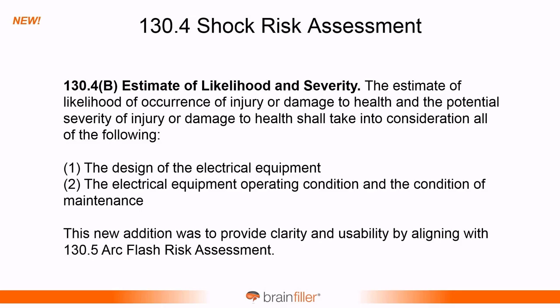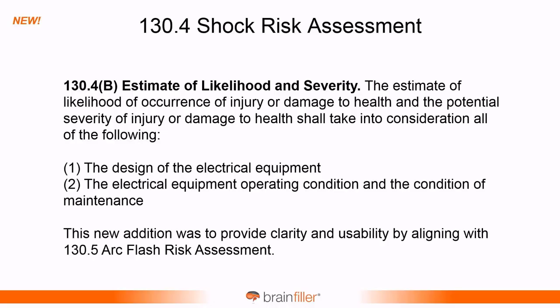The shock risk assessment. So there was language that is part of the arc flash risk assessment that has now been duplicated, and what that language looks like right here. Estimate the likelihood and severity. The estimate of the likelihood of occurrence of injury or damage to health and the potential severity of the injury or damage to health shall take into consideration all of the following. Number one, the design of the electrical equipment. Number two, the electrical equipment operating conditions and the condition of maintenance. And so this is really to align it with what we already had in 130.5, because the same type of language exists for the arc flash risk assessment.